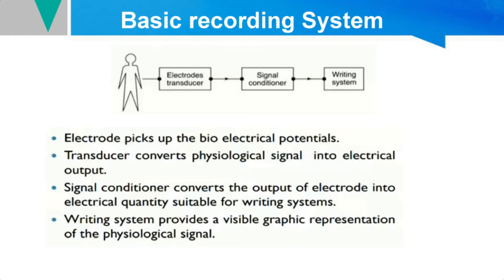The biological signal picked up by the electrodes is then passed through a transducer. The transducer converts any physiological signal into an electrical signal. This electrical signal is then given to a writing system or output unit through the signal conditioner. The signal conditioner modifies the input into a suitable form that can be understood by the display unit — which could be a pen recorder, a graphical chart, or a CRO where the biological signal output can be seen.